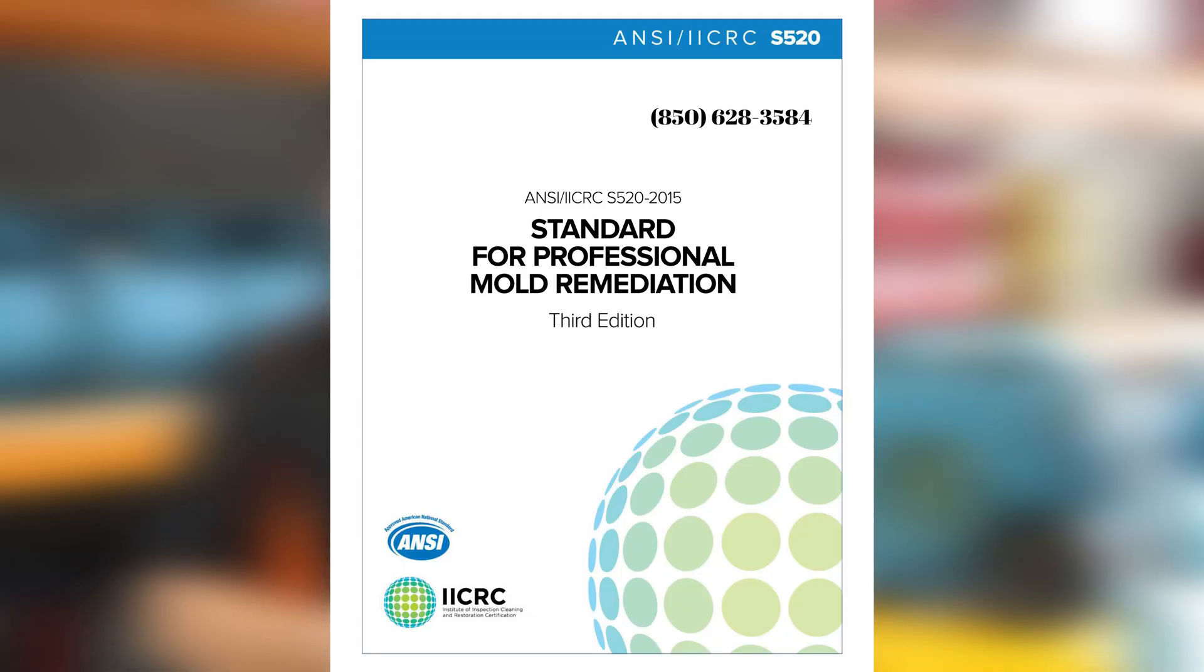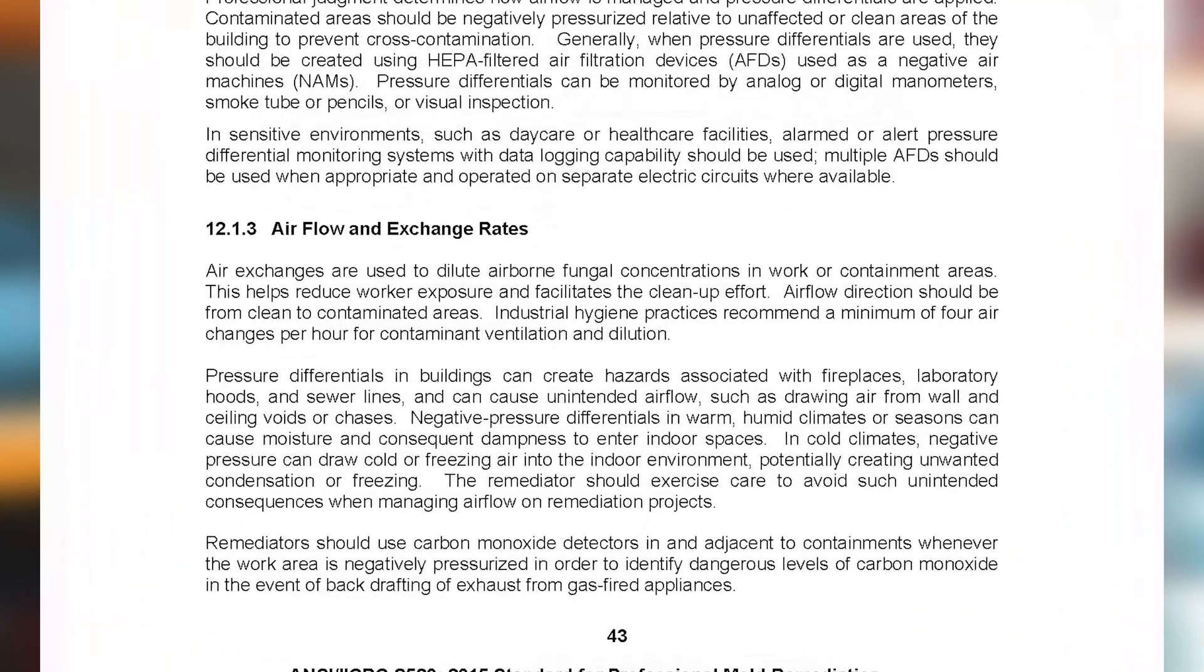The IICRC S520 standard for mold remediation advises for small demolition works or after a small clean water damage, one to two air changes per hour should suffice. However, for mold you'll need a minimum of four air changes an hour under negative pressure.